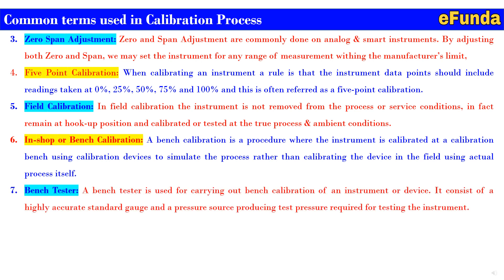Seventh is the bench tester, which is used for carrying out bench calibration of an instrument or device. It consists of a highly accurate standard gauge and a pressure source producing the test pressure required for the instrument. Most benches are fabricated on the job site by the instrument technician, while some are ordered as a complete system from the vendor as a ready-made test bench setup.